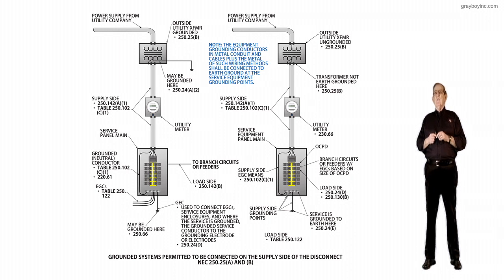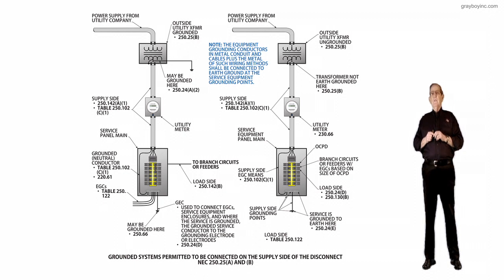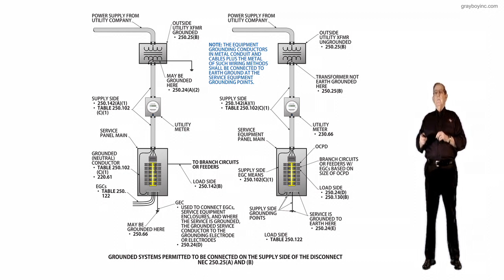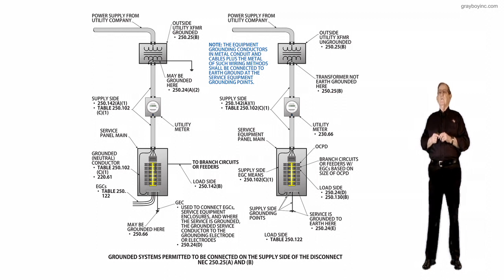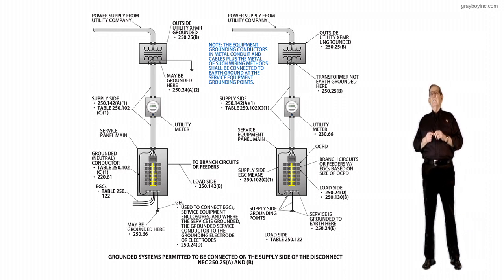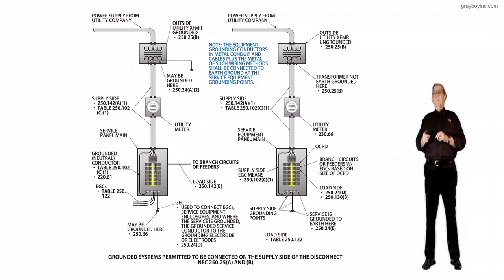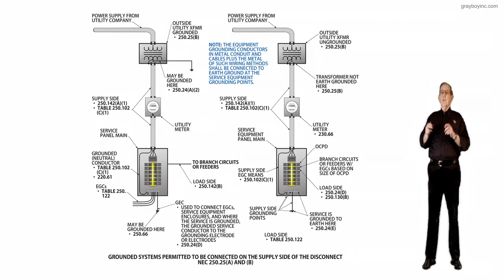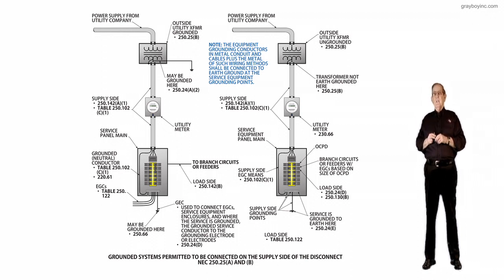Now, the panel board transformer to the left is grounded, and we just pull in a chassis ground. But the chassis ground has to be installed now by 250.102(C)(1), by this section. And again, it's referring you to 250.24 to obtain this information. The meter marking and everything is in 230.66, and it's not considered a service. But to the right here, that transformer is ungrounded. So we're looking at maybe 250.121, or we're looking at Article 90 in the National Electrical Code.